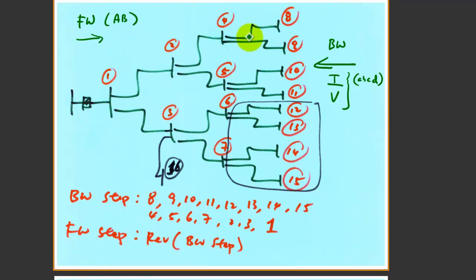So this is a forward step and backward step. As I enumerate all this, the backward step goes 8, 9, 10, 11, 12, 13, 14, 15, then later 4, 5, 6, 7, then 2, 3, then 1. The reason we go through this sequence is that it gives you the information you need before you compute the sum of current at node 4, node 5, node 6, and node 7. For example, for node 5, without computing node 10 and 11, you can't find out the total current you need.